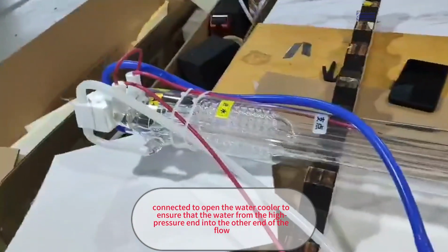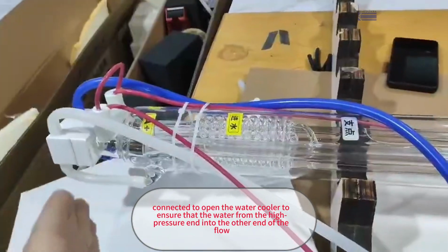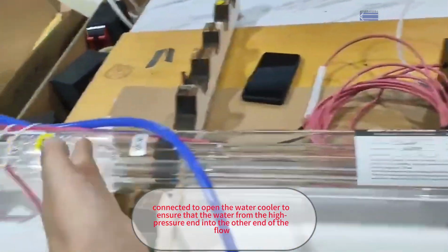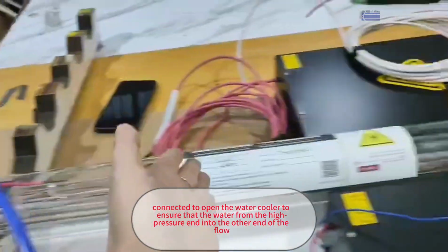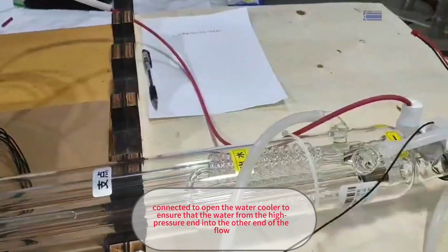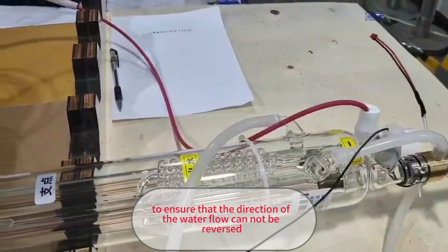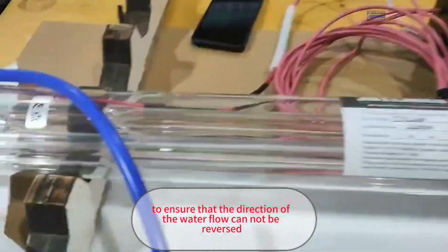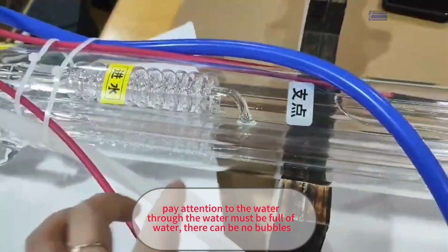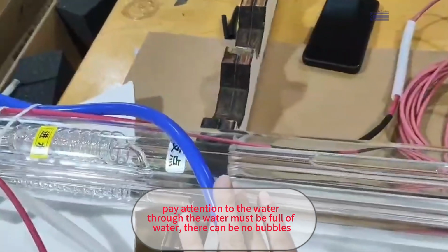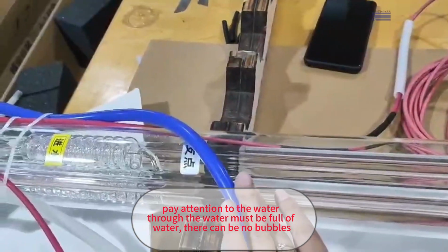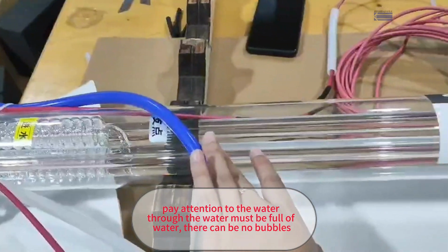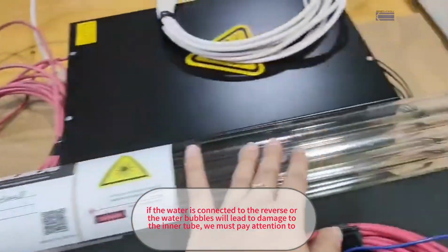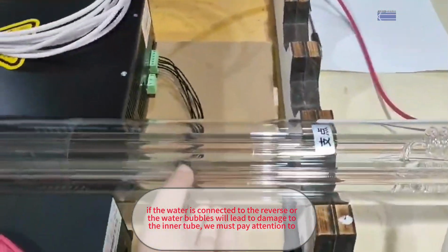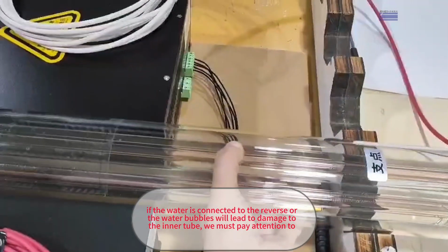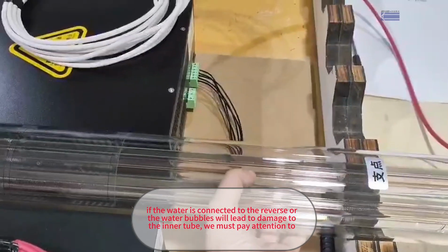Once connected, turn on the water cooler to ensure water flows from the high pressure end into the other end. Make sure the direction of water flow is not reversed. The water tubing must be full of water with no bubbles. If the water connection is reversed or there are bubbles, it will damage the inner tube, so pay close attention to this.